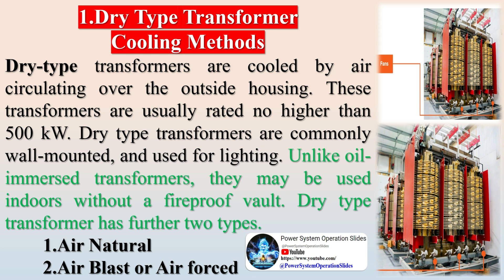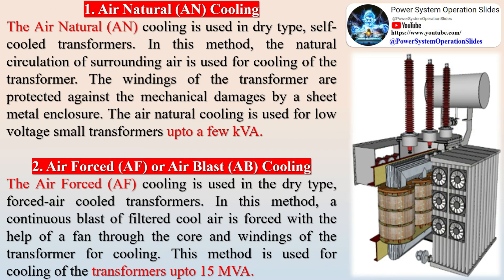Air Forced (AF) or Air Blast (AB) cooling is used in dry type, forced air cooled transformers. In this method, a continuous blast of filtered cool air is forced with the help of a fan through the core and windings of the transformer for cooling. This method is used for cooling transformers up to 15 MVA.